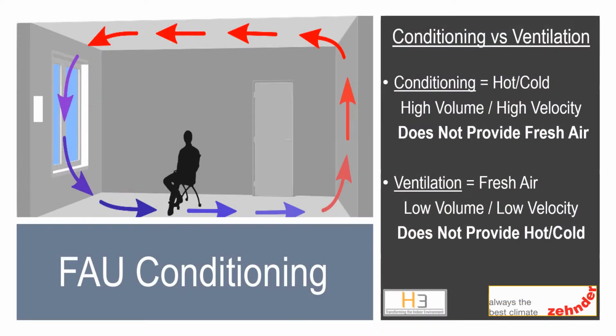We want to reiterate the difference between conditioning and ventilation. Forced air units are an example of conditioning. These systems roll air around the circle, providing heating or cooling. This is done at high volume and high velocity to supply and return large amounts of air. Ventilation systems like HRVs provide continuous, balanced fresh air to the occupants. They do not provide heating and cooling, but conserve the energy that conditioning provides. These are low flow, low velocity systems and require smaller ducting that is designed to optimize distribution of this fresh air.